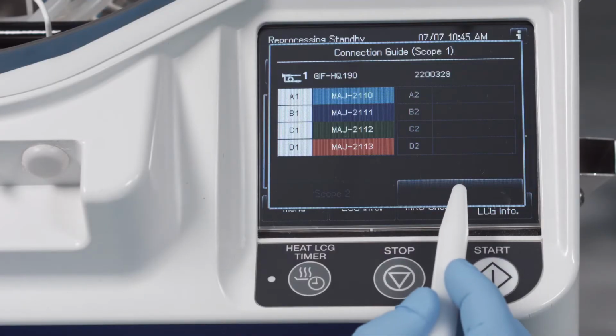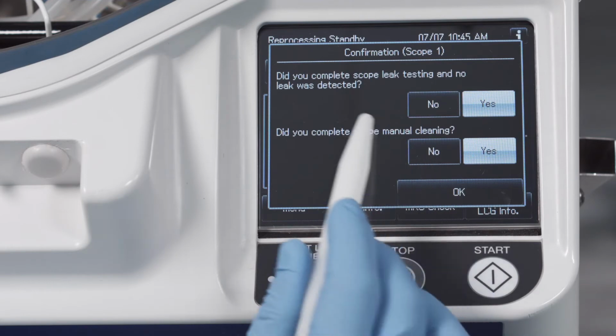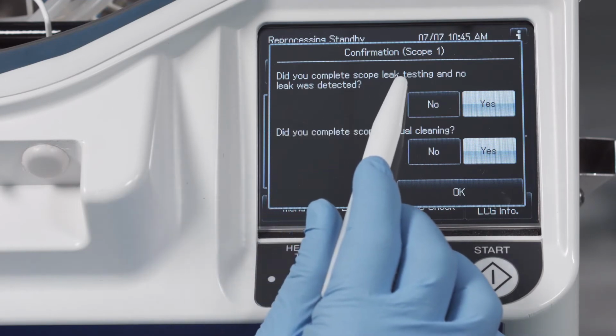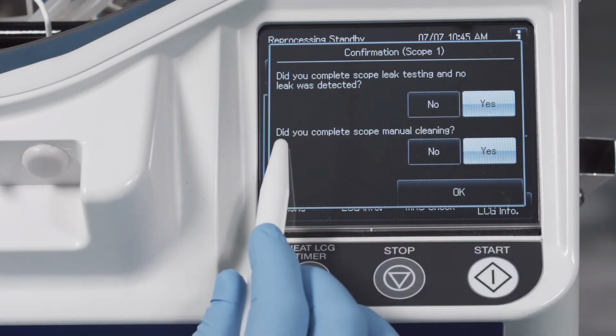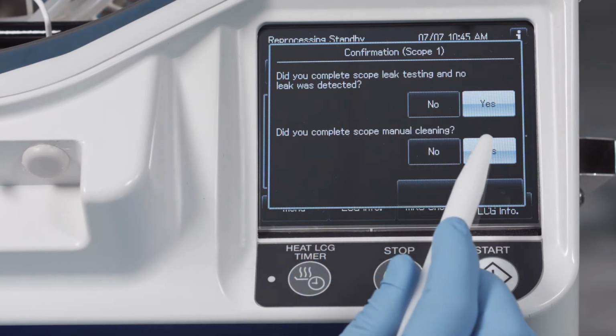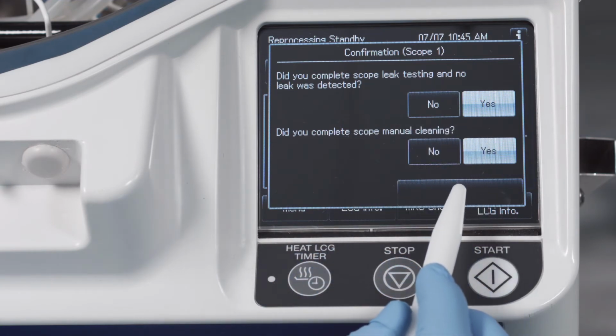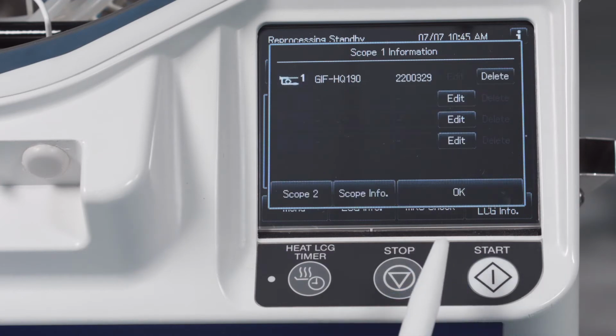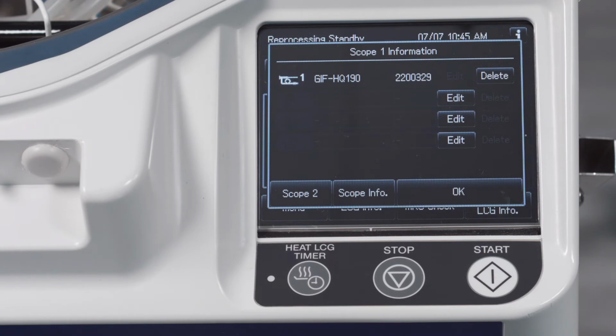Now, confirm that the leak test has been performed with no leaks detected and that the manual cleaning has taken place with this endoscope, as mandated in the scope's reprocessing instructions. Once completed, confirm Yes on this confirmation screen, followed by OK. If these required steps have not been performed, please refer to your endoscope reprocessing instructions in order to complete the reprocessing steps necessary prior to loading the endoscopes into the OER-Elite.